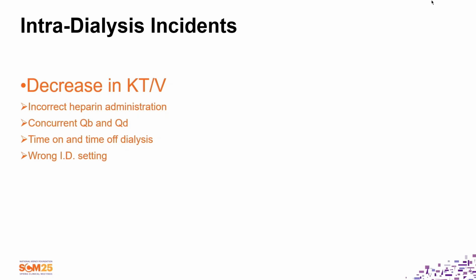Okay. Wrong ID setting. Some machines have the 6.3, 8.8 setting. So if you do have the wrong setting, it'll give you the readout, but the rotation of the blood pump will be different. Note that in a layman's approximation, each rotation of the blood pump roller is how much? You can literally guess and approximate your blood flow by counting the revolutions of the blood pump. Each revolution of the blood pump is approximately 10 cc's. So if you're at 200, 20 times. So if you're ever in question that your blood flow is not where it's supposed to be, do an approximation by counting the revolutions. 10 cc's per revolution.